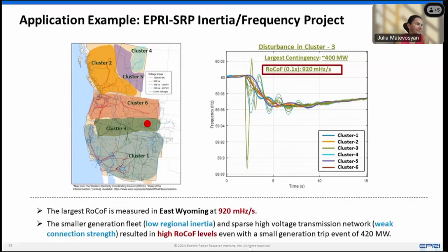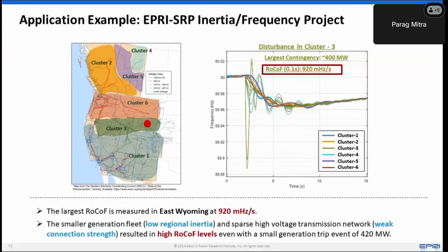The short answer is the algorithm tries to look for the electrical closeness of generators together. And it's not just the electrical closeness, it's defined by the susceptance divided by the inertia, that ratio, which is used to identify which groups are expected to have a coherent dynamic during a frequency event.